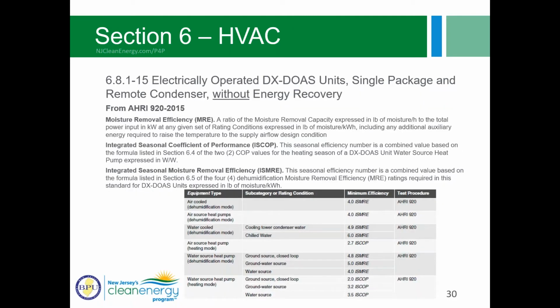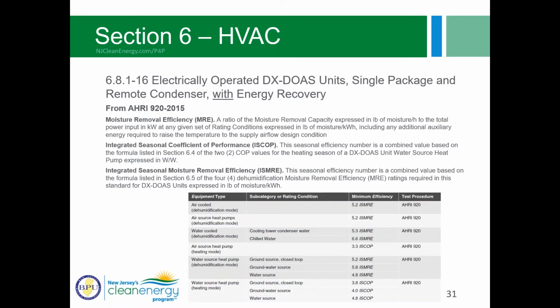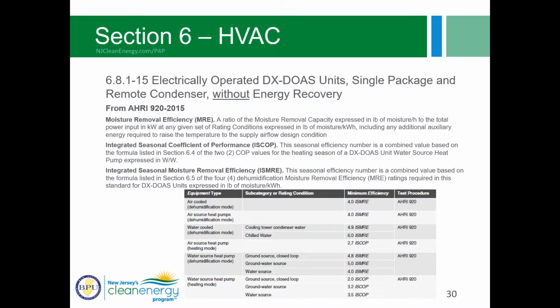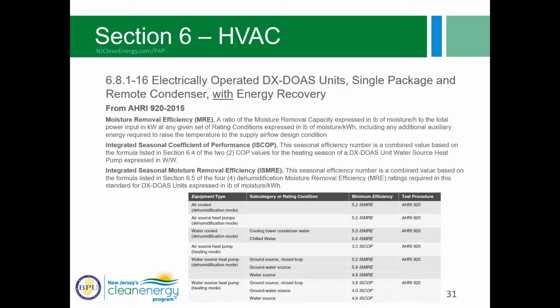All right. So with the DX dedicated outdoor air systems without energy recovery, these weren't previously in 90.1 2013. So now we have a table for without energy recovery, and there is similarly a table for with energy recovery. So we have two new tables for minimum efficiencies. So again, 15 is without, 16 is with energy recovery.